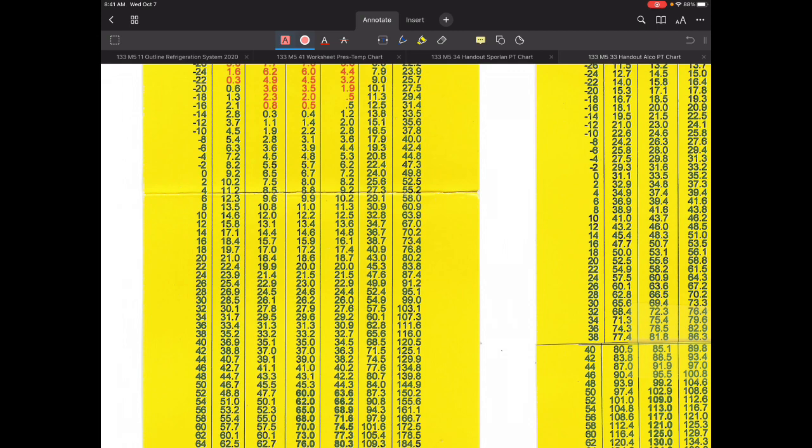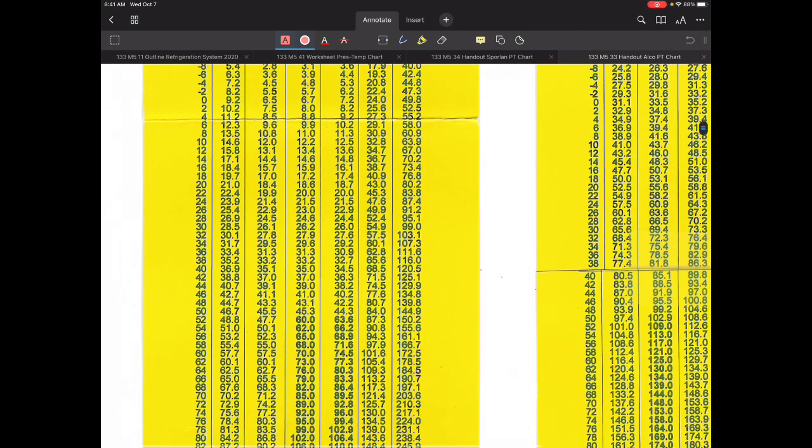So it's a little bit less pressure than the 120 psi that was identified. So let me see if I can circle that. So in this case here, we've got R410A, 120 psi, so right there. And of course, that would tell me that the saturation temperature would be probably the closest to 40 degrees Fahrenheit, in my opinion.